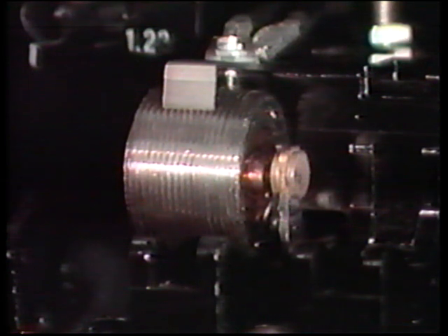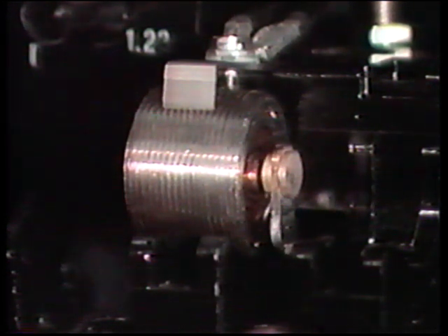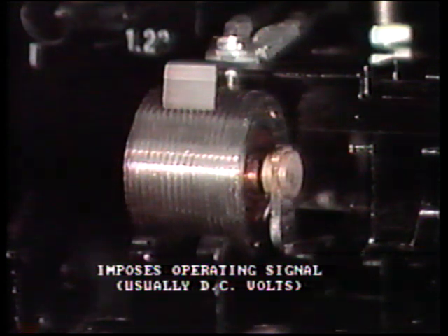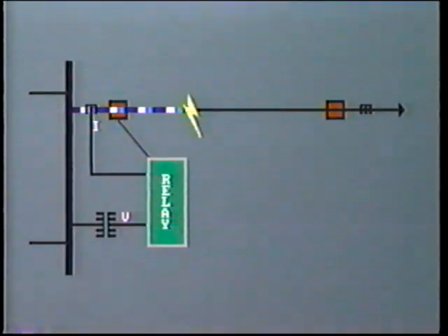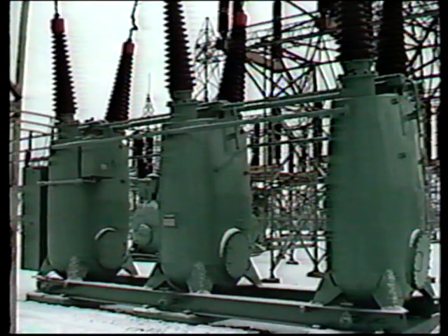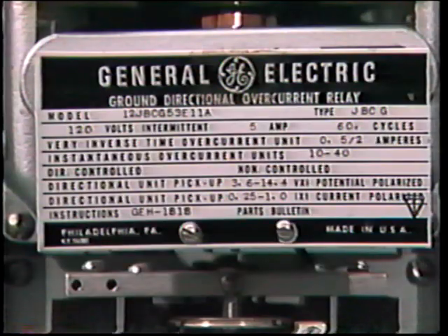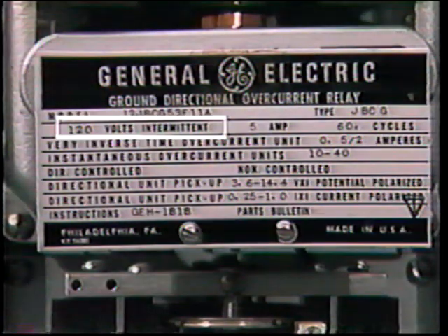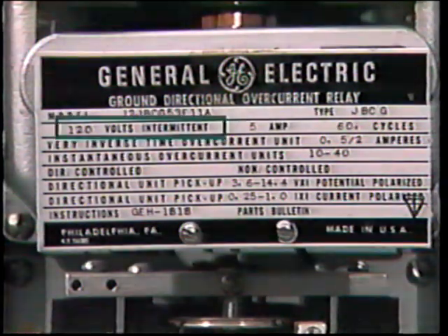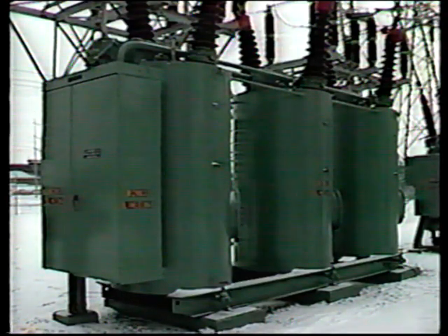That is, a set of open or closed contacts at rest. However, with an intolerable fault level, then the relay output will impose an operating signal on a control circuit, usually in terms of DC volts. This tripping signal is then fed to one or more circuit breakers to cause them to open so as to isolate the faulty circuit. What is the purpose of the circuit breaker? Well, obviously, the relay itself is a small, low-voltage control device, whereas the circuit breaker is an integral part of the high-voltage, high-current power system.